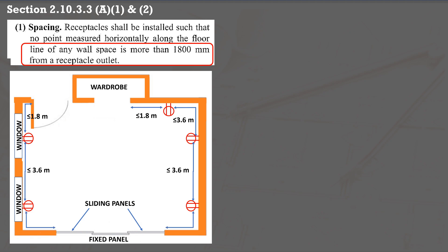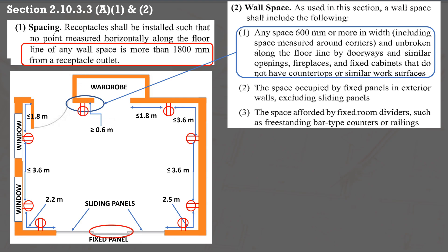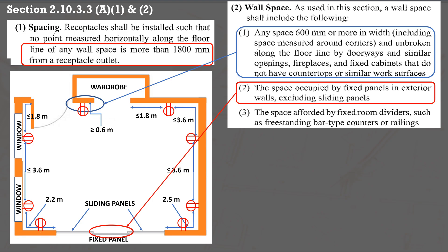Ensure that no point on the wall is more than 1,800 mm from a receptacle outlet. Hence, check the distance between the edge. If these are more than 1,800 mm, additional outlets must be provided. For a short wall space, in paragraph A2, if the length of the wall is 600 mm or more, an outlet will be required. Further, for a fixed panel mentioned in paragraph A2 item 2, a fixed panel is considered wall space.